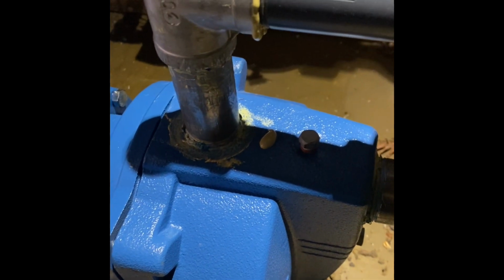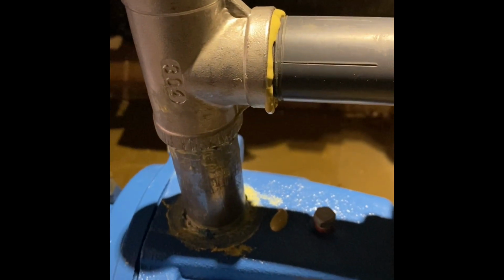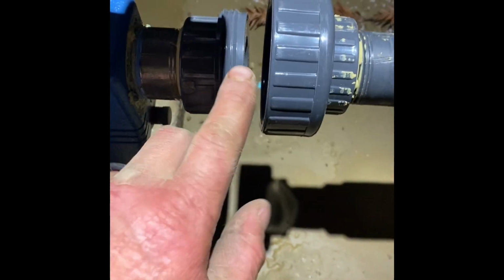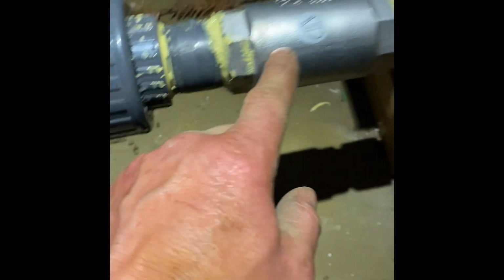Okay, so put all the fittings on. I use stainless steel so they don't rot out, and I don't use plastic because they get hot. Schedule 80, this will get hot but not as fast. This is stainless steel down here. And then I have a union. There could be a union there too coming off. Another Schedule 80 nipple and a brand new check valve.